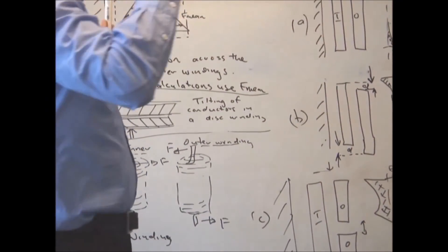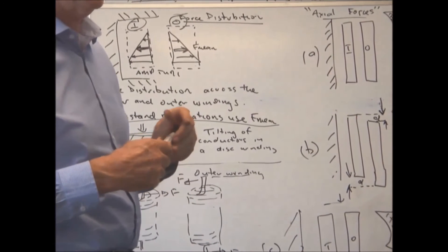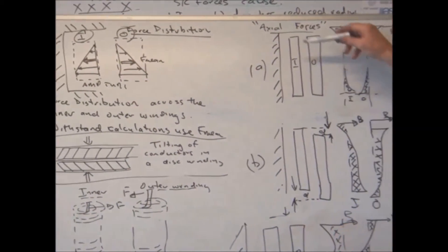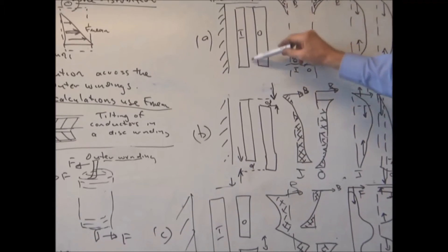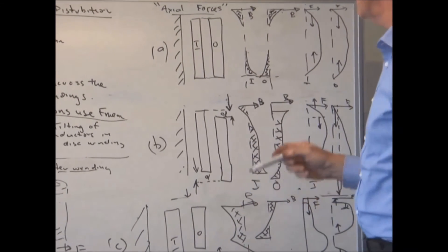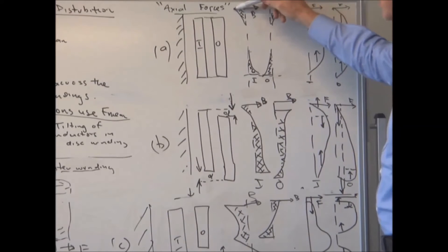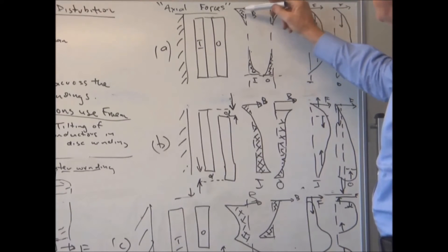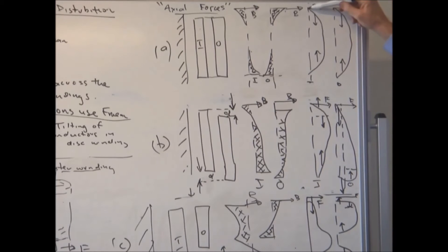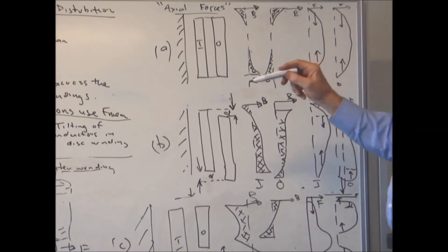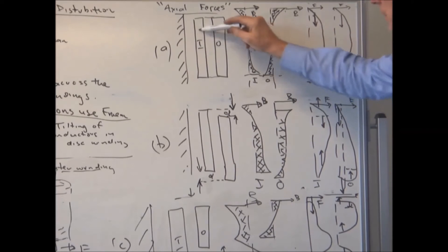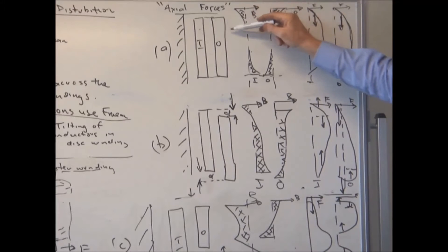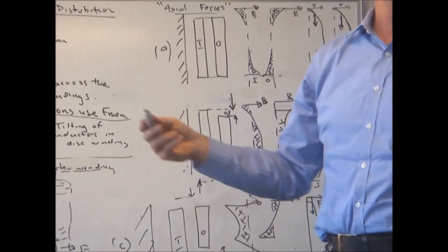Now, looking at combinations depending on how the windings are configured: here the inner winding and outer winding are drawn with the same length — they are not axially displaced. The leakage field on the inner winding looks one way, and the field on the outer winding has a corresponding shape. In terms of axial forces, the forces are pushing down on both windings symmetrically, gradually building up from the ends due to the shape of the leakage field.